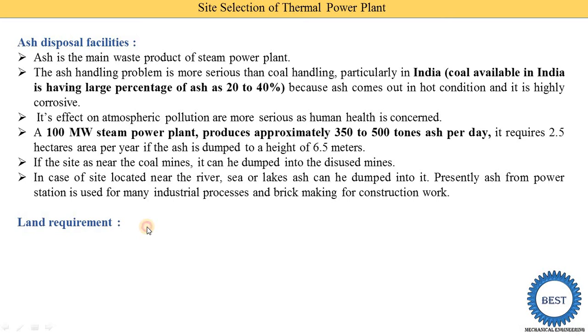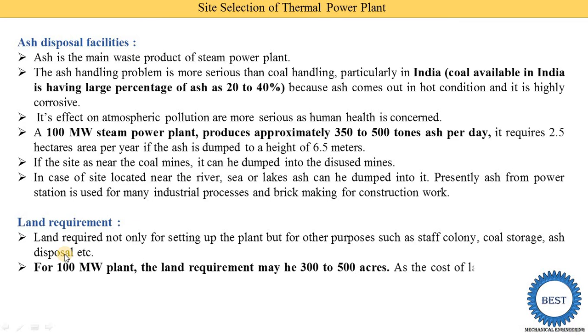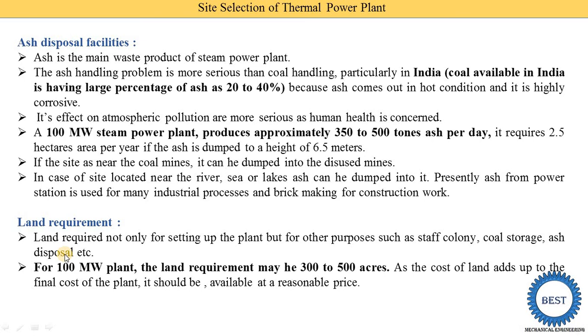Next point is the land requirement. Land is required not only for setting up the plant but for other purposes such as staff colony, coal storage, and ash disposal. For coal storage and ash disposal, very large space is required compared to the plant setup itself. For a 100 megawatt plant, the land requirement may be 300 to 500 acres. The cost of land adds to the final cost of the plant, so land shall be available at a reasonable price. Land should also be available for future extension.